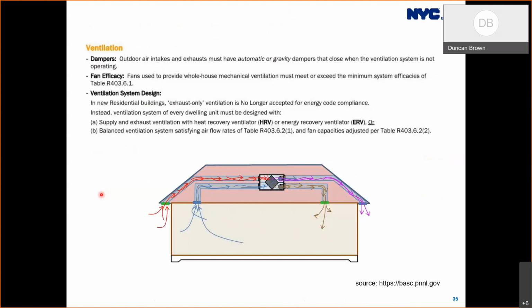So in terms of the how-to guide, we lay out that for ventilation, dampers are straightforward and typically provided as part of mechanical equipment. Fan efficacy is also straightforward to document, but the more difficult issue is the ventilation system design. So in new residential buildings, exhaust-only ventilation is no longer accepted for energy code compliance. Instead, the ventilation system of every dwelling unit must be designed with a supply and exhaust ventilation system with a heat recovery ventilator or an energy recovery ventilator. Or, and the last point B there, a balanced ventilation system satisfying the airflow rates and fan capacities in the code is also a possibility. But we're typically not seeing many people able to satisfy the requirements of those tables.